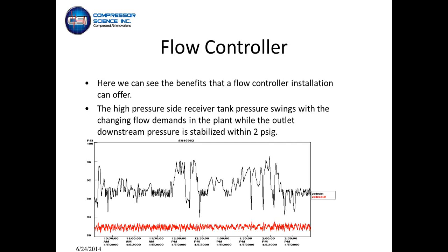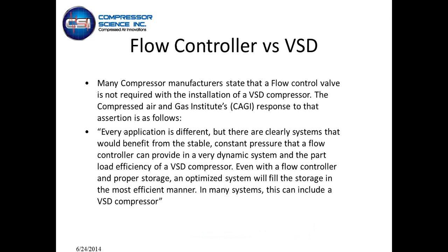This graph of a flow controller installation will give you an example. On the high pressure side, you can see on the black line where the receiver tank is now going up and down in pressure, but the discharge side of the receiver through the flow control valve is maintaining a steady 1 or 2 psi out into the distribution system. So the purpose of the valve is to open up and allow the volume out that you need, but doing it at a steady state pressure within a couple of pounds. That's what limits the velocity through the system, but allows the flow out that's needed for production.